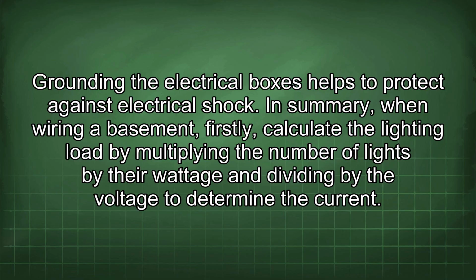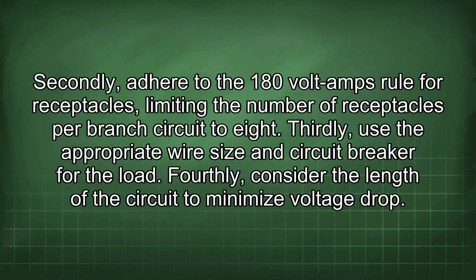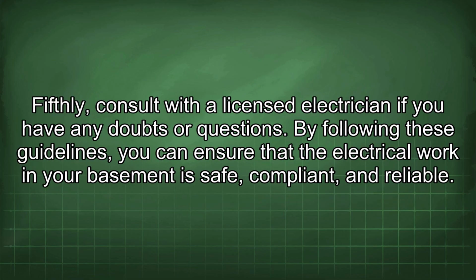In summary, when wiring a basement, firstly calculate the lighting load by multiplying the number of lights by their wattage and dividing by the voltage to determine the current. Secondly, adhere to the 180 volt-amps rule for receptacles, limiting the number of receptacles per branch circuit to 8. Thirdly, use the appropriate wire size and circuit breaker for the load. Fourthly, consider the length of the circuit to minimize voltage drop. Fifthly, consult with a licensed electrician if you have any doubts or questions.